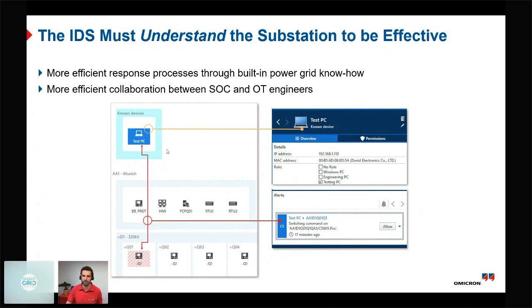This is an example of a screenshot of an IDS. Here we see an alarm going from a testing PC, the engineering laptop mentioned before. We immediately see in the picture that the 320 kV voltage level, bay number one, bay controller was involved. The alarm messages are clearly understandable so that protection and control engineers and IT security officers can work together in diagnosing this alarm quickly.